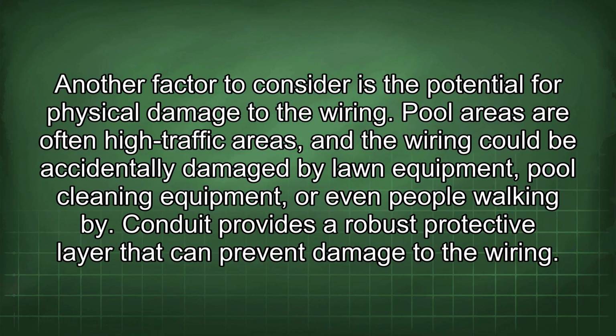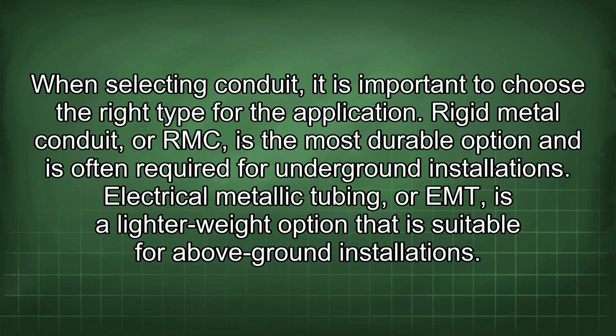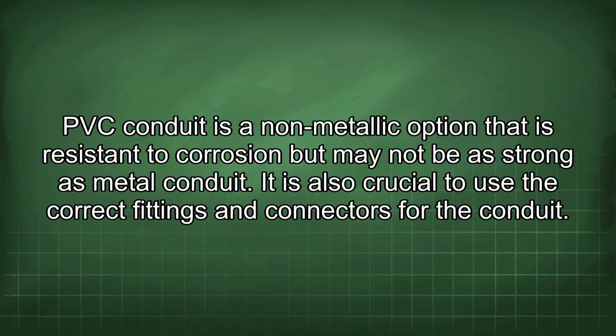Another factor to consider is the potential for physical damage to the wiring. Pool areas are often high-traffic areas, and the wiring could be accidentally damaged by lawn equipment, pool cleaning equipment, or even people walking by. Conduit provides a robust protective layer that can prevent damage to the wiring. When selecting conduit, it is important to choose the right type for the application. Rigid metal conduit, or RMC, is the most durable option and is often required for underground installations. Electrical metallic tubing, or EMT, is a lighter weight option that is suitable for above-ground installations. PVC conduit is a non-metallic option that is resistant to corrosion, but may not be as strong as metal conduit.